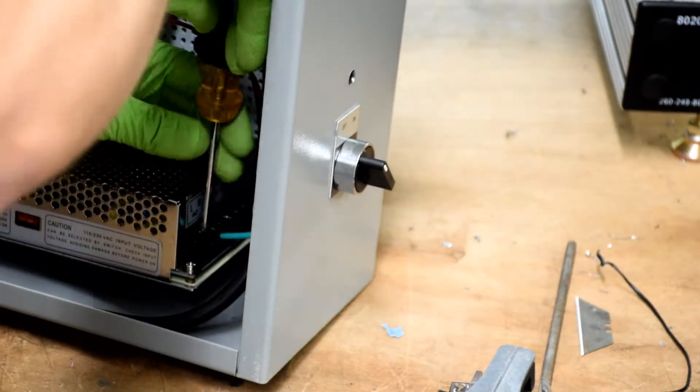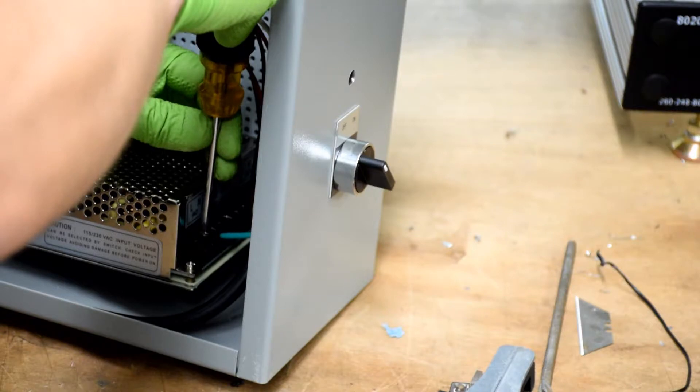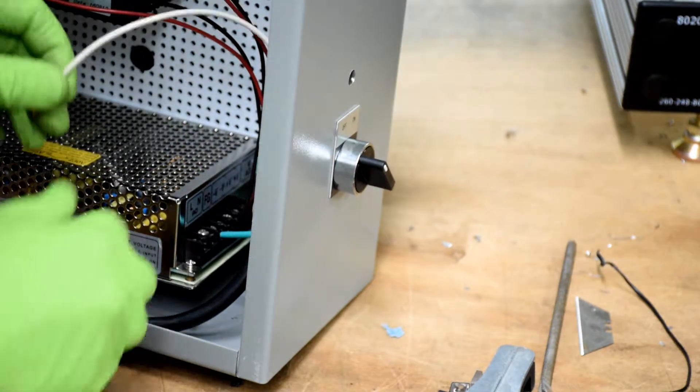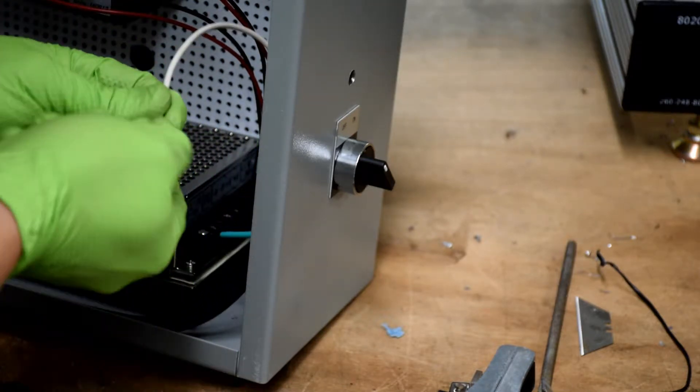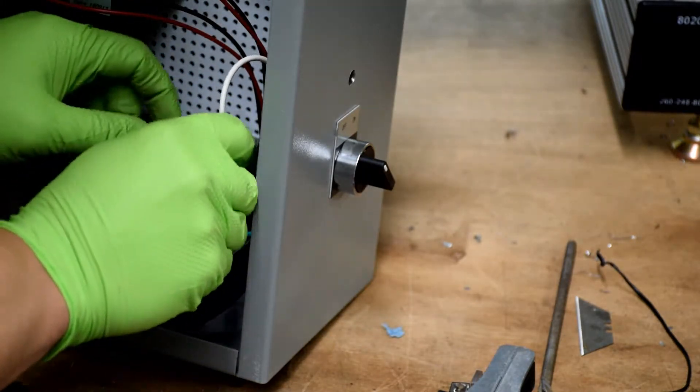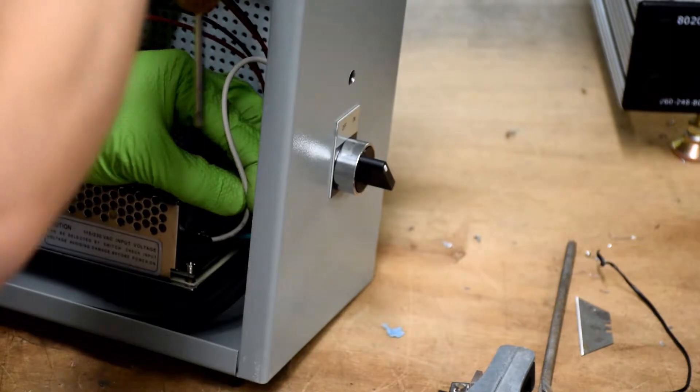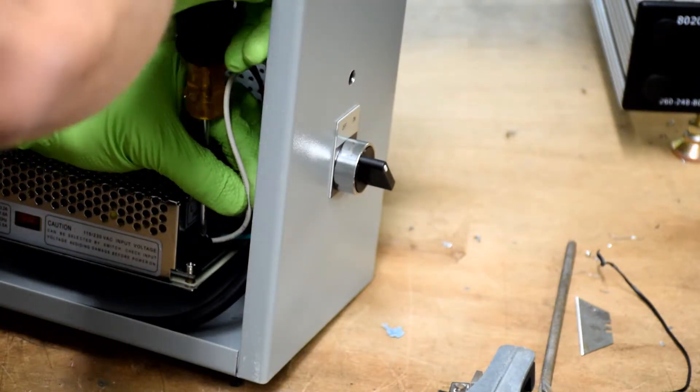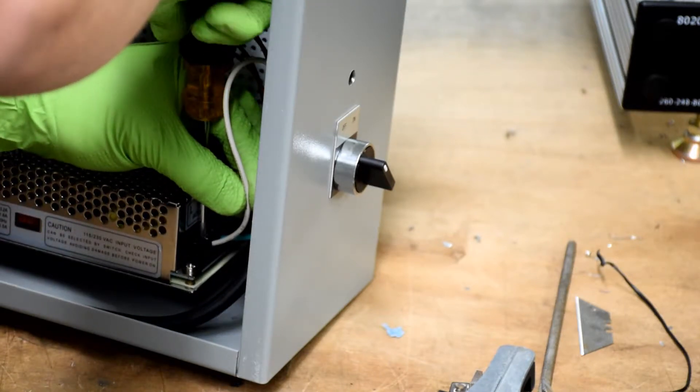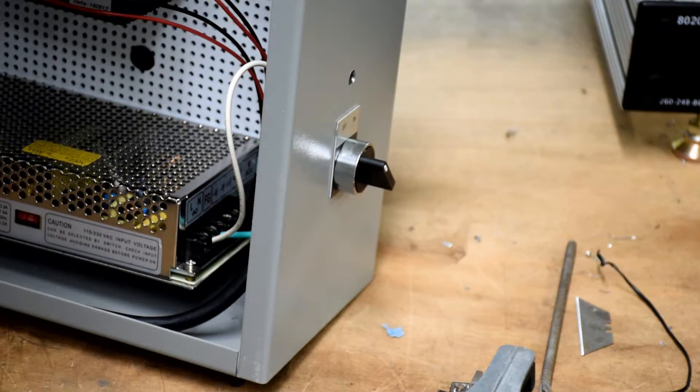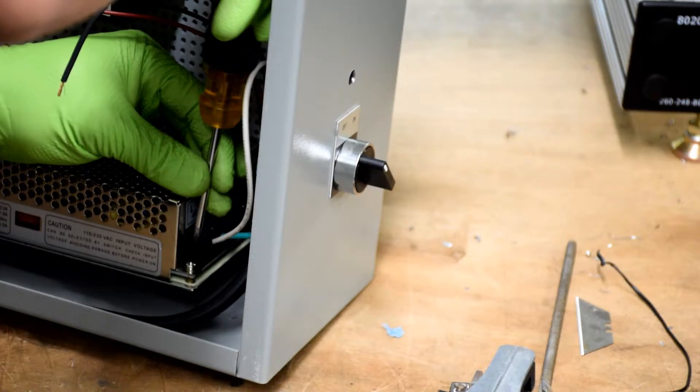First, I'm going to run the white wire into the neutral terminal on the power supply. And that's the terminal that says N. After you tighten your connections, always give your wires just a little tug just to make sure that they're in there and seated properly. You really don't want any loose connections.